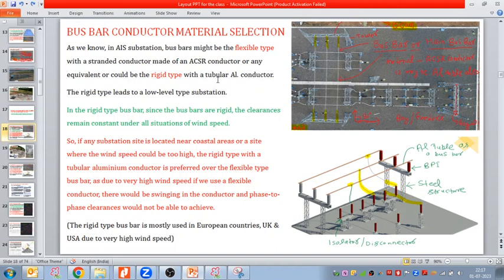Tubular, not the solid tube, a hollow tube aluminum conductor. The rigid type leads to a low level type substation. The height of installation is very low, so it leads to a low level type substation. In addition, since the bus bars are rigid with the aluminum tube, the clearances remain constant under all situations of the wind speed.